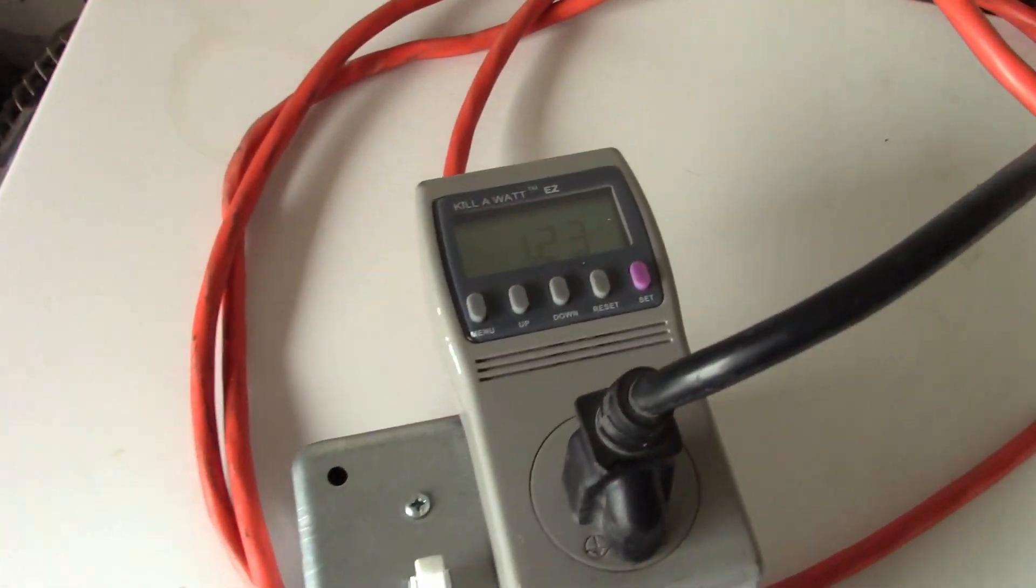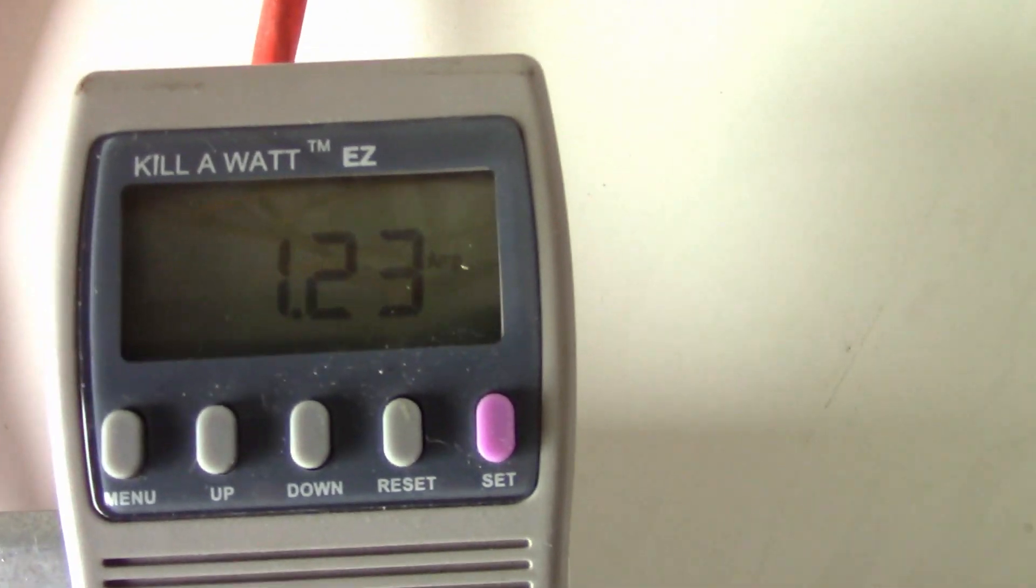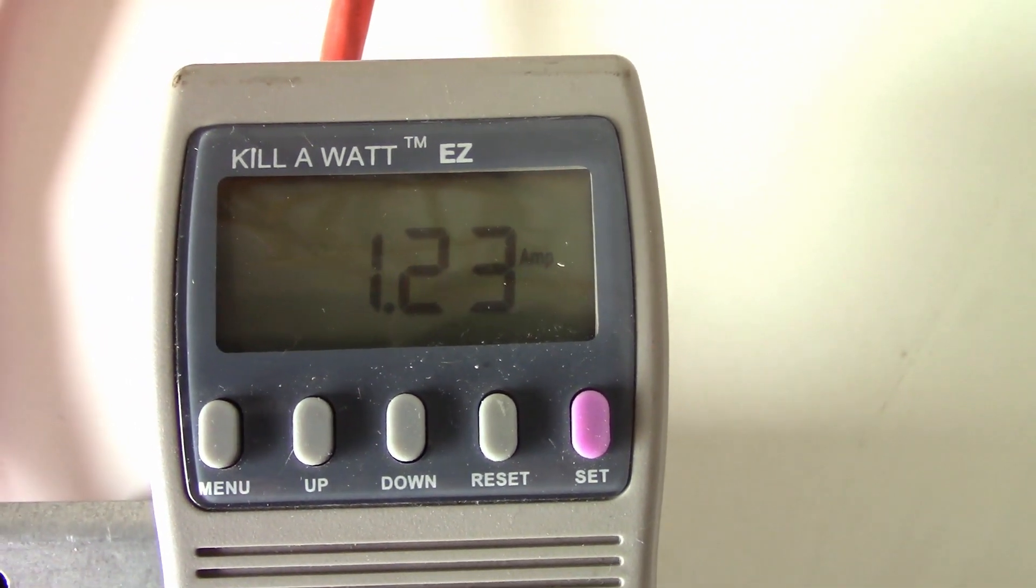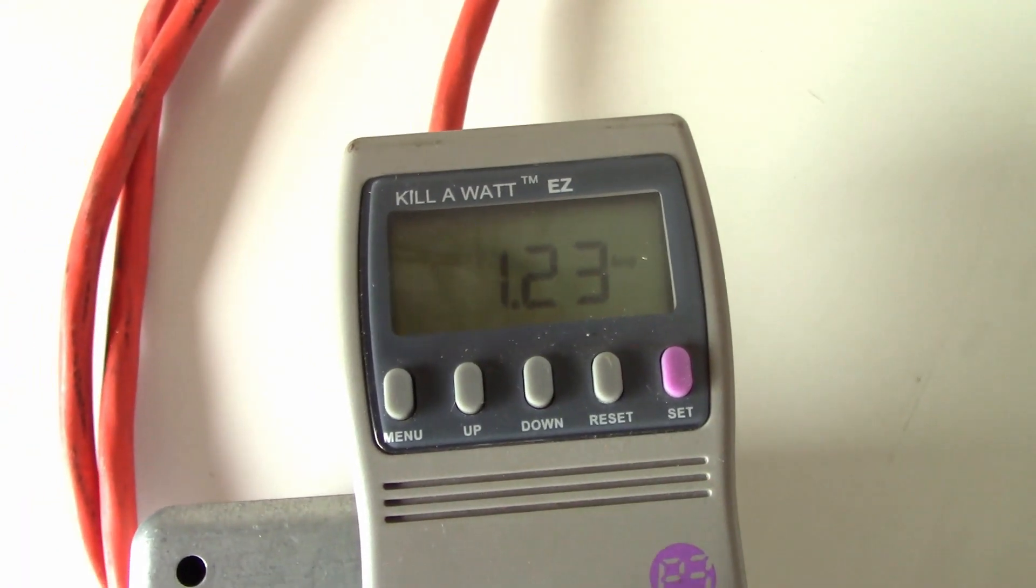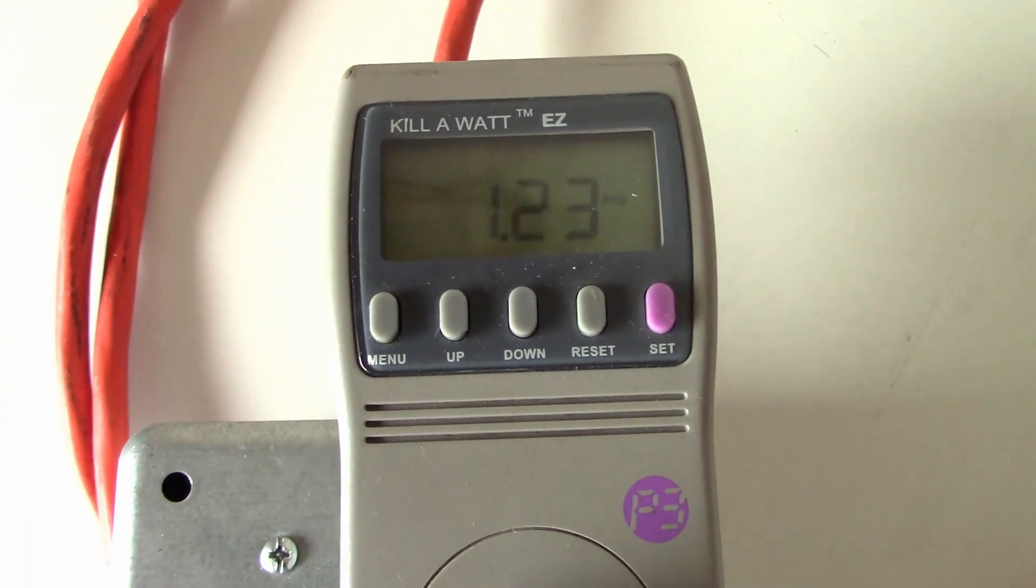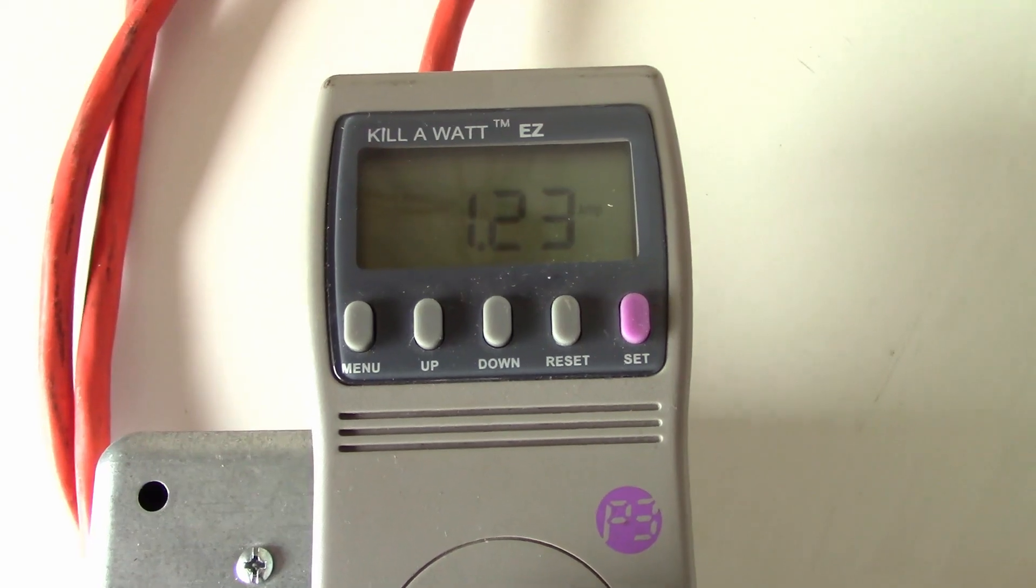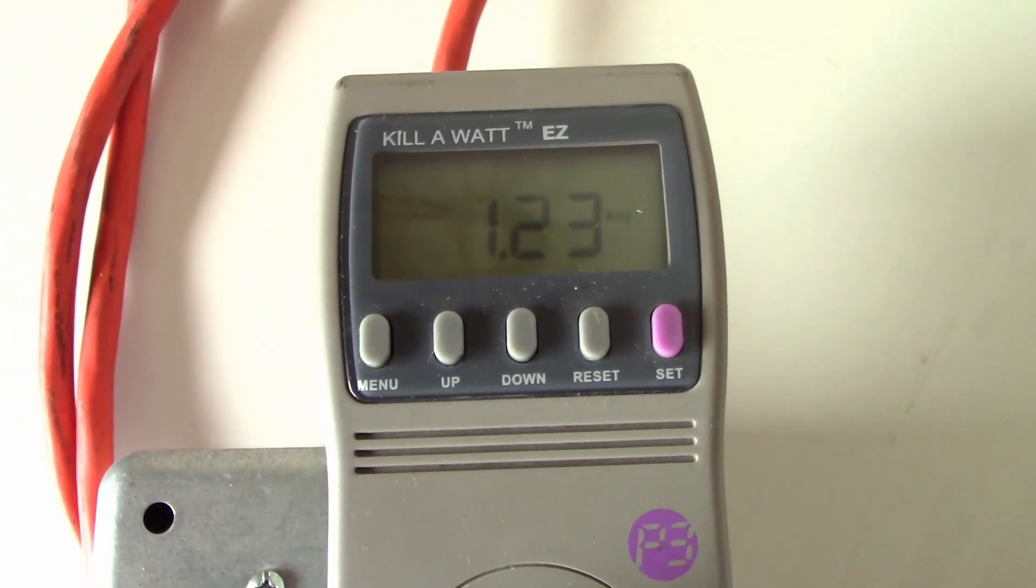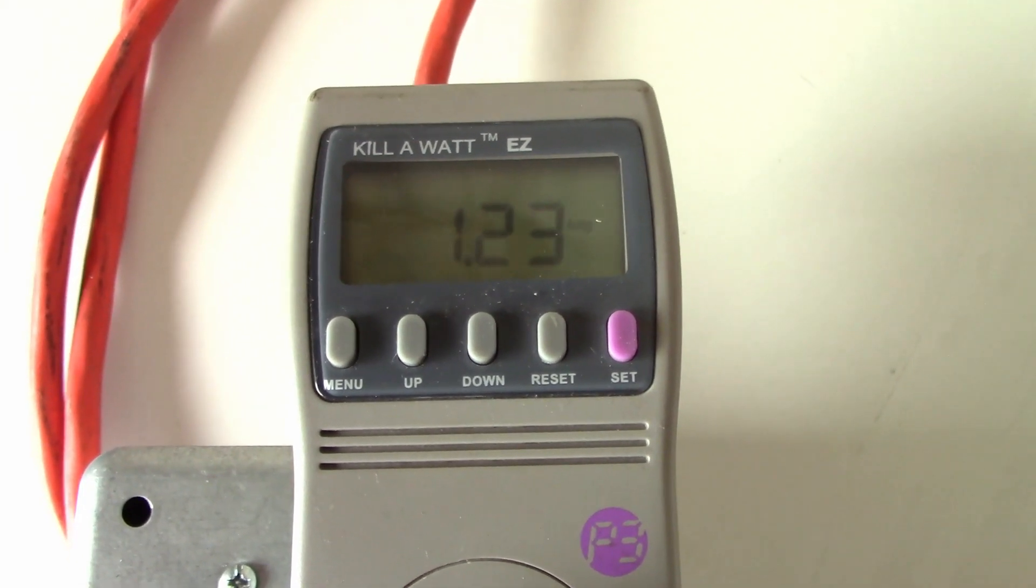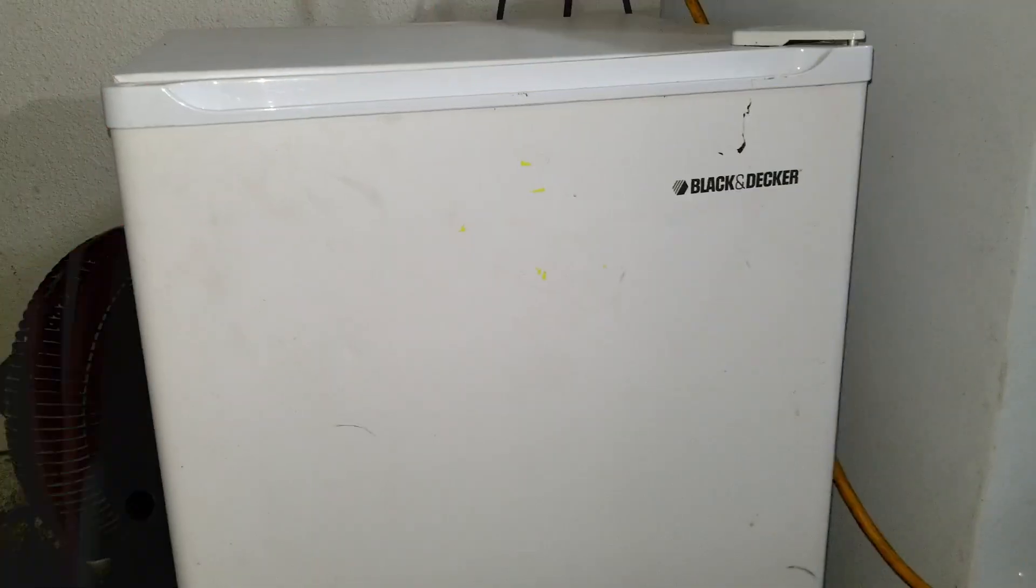With parts on hand, I just happened to have the Omron timer and the relay to get this job done successfully. I did go ahead and set the initial time to 2 tenths of a second. It started good at 3 tenths. I even tried it with 1 tenth of a second and it barely started, so I went ahead and made it 2 tenths. It's starting quite reliably at this point.